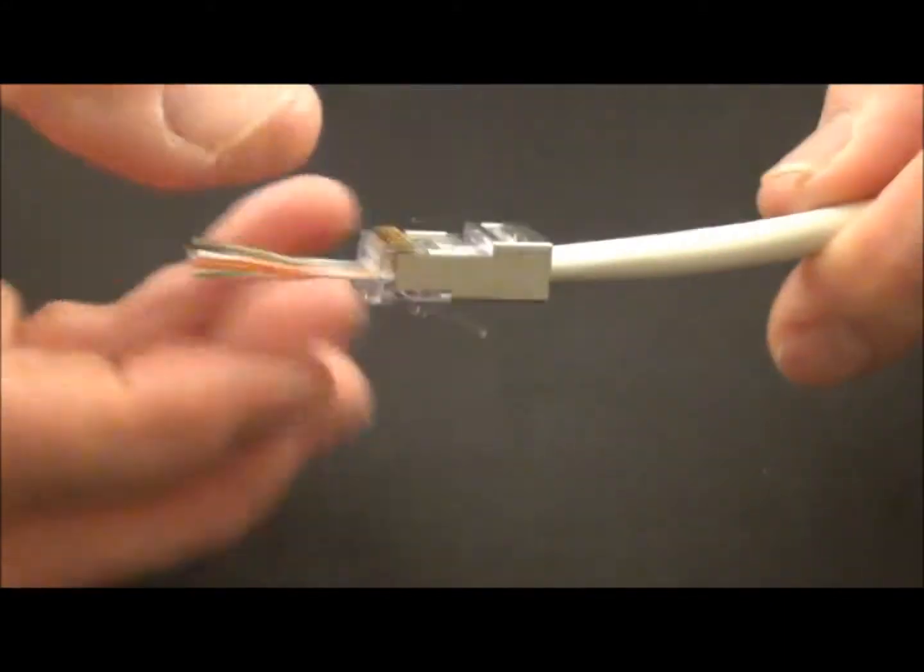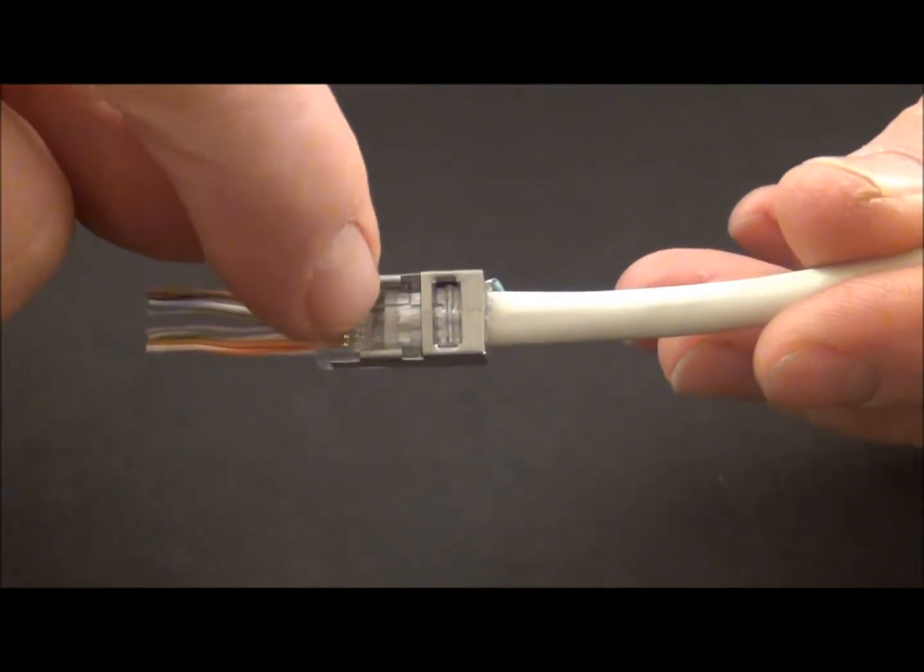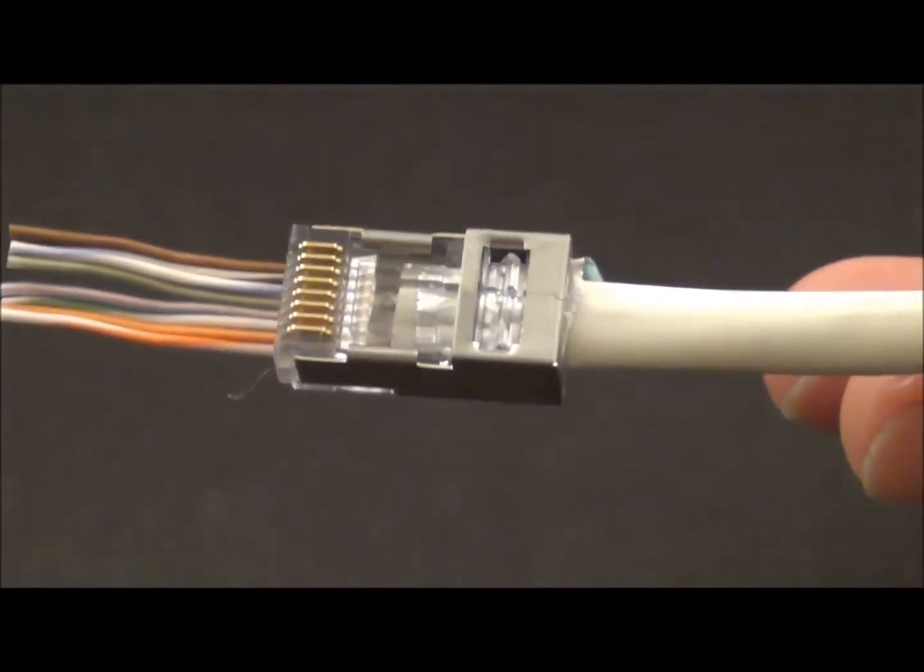Stop at that point and I'm ready to do my crimp. You'll notice I've set my jacket even further than it needs to be. The closer the twist to the point of termination, the higher the performance.